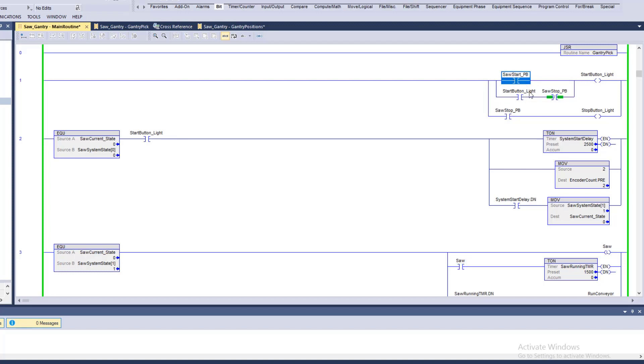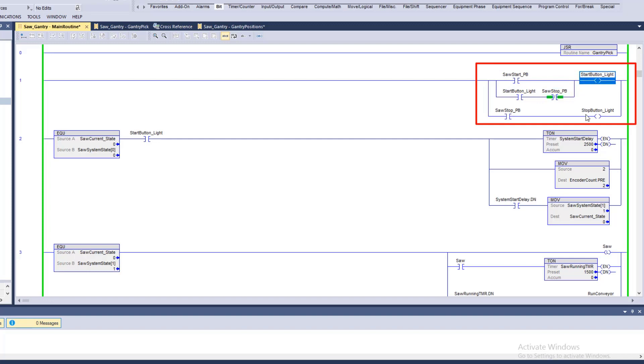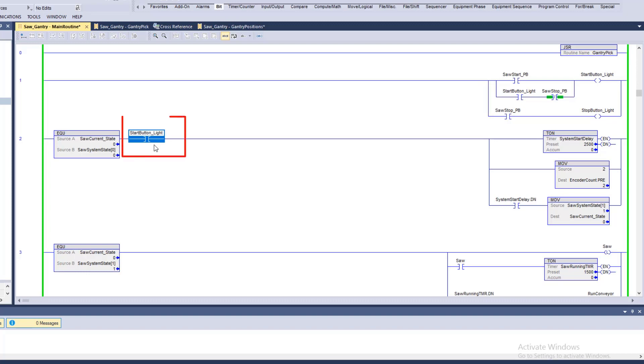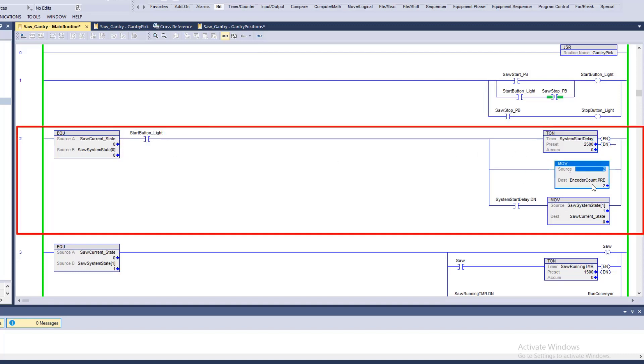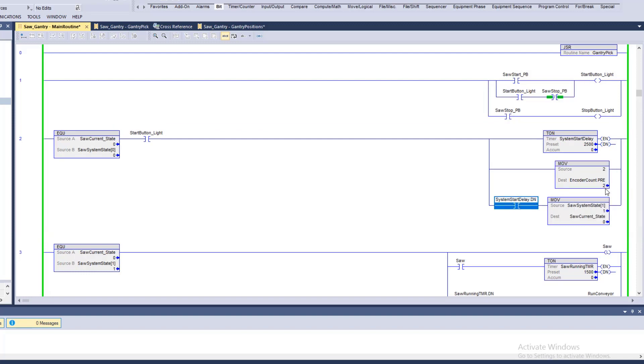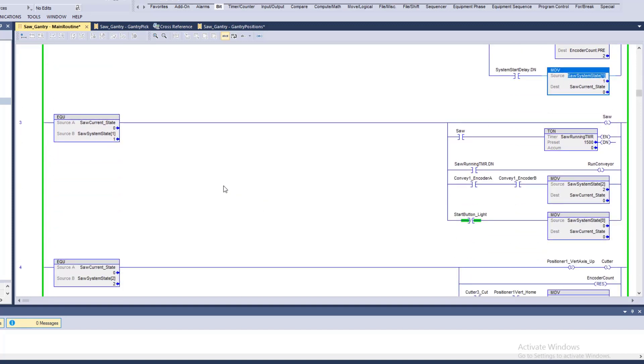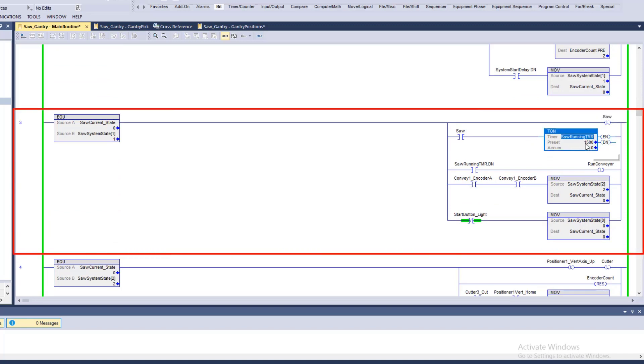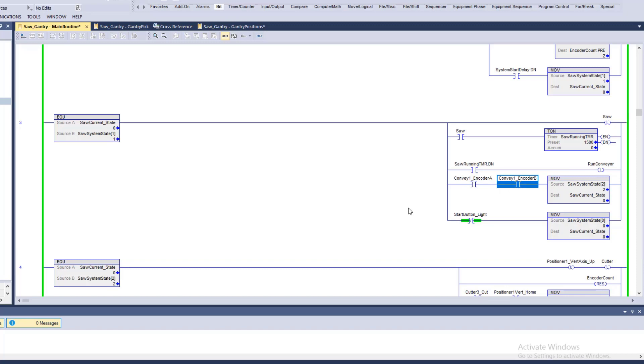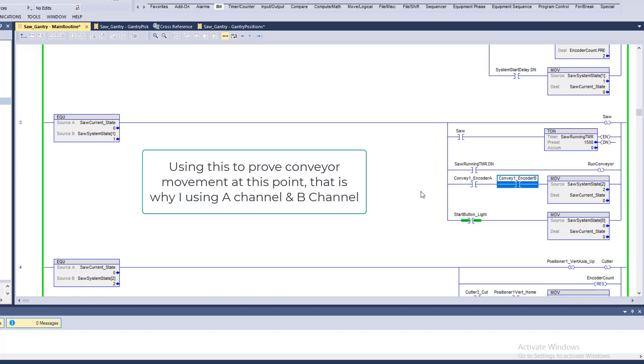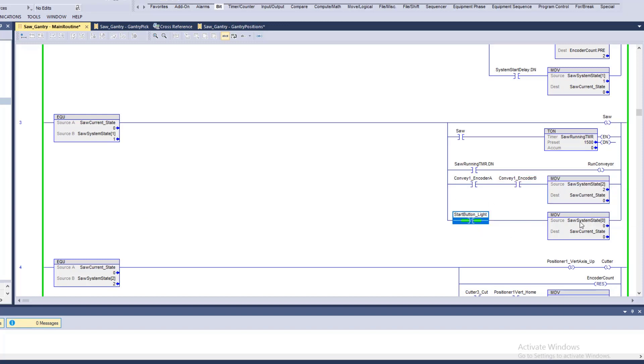We have a start/stop push button station. It's going to cut on a light — I'm using the light as my system active bit. If it's in state zero and the system is active for two and a half seconds, it will preload the encoder count preset, which determines the length of wood where it's chopped. After two and a half seconds it goes into state one, turns the saw on, and after a second and a half turns the conveyor on. It then looks at encoder counts: when A and B channels are both on, there is activity on the encoder and the conveyor is running — then we move into state two.